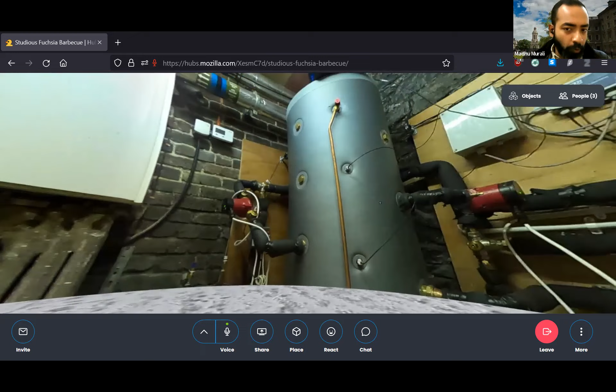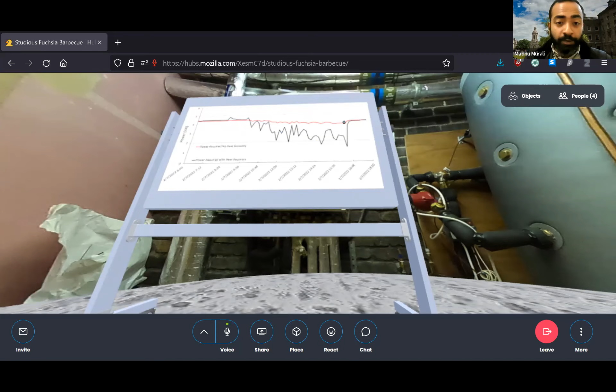I've got a graph over here as well to talk about a couple of things. This is another day of the system operating, and we've got two lines, the red line and the black line. The red line is the power that would be required if there was no heat recovery being operated, in the range of about 4.5 kilowatts for the kitchen. Along the day there's a bit of variation. When the kitchen starts being used around 9:30 to 10, the power required to heat the water goes lower and lower as we recover more and more heat from the wastewater coming out. At certain points it's almost less than half the actual requirements.